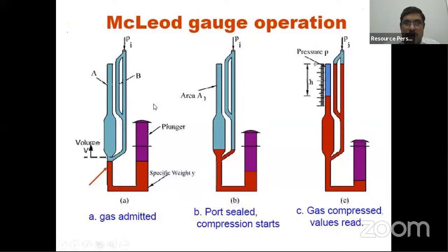First you admit the whole gas till a certain point, then you press the plunger till this point, where there is a mark. At this mark, your P1, the unknown pressure of the gas, will be equal to the pressure maintained in the so-called bulb volume. So the volume of the bulb multiplied by P1 will be equal to this. Now you pressurize it further and reach the scale. Once you reach the scale, you get the value of H, and from the value of H you can get the value of pressure.